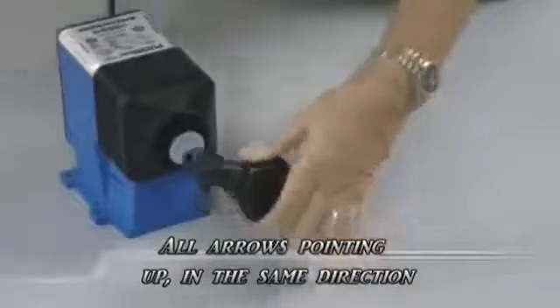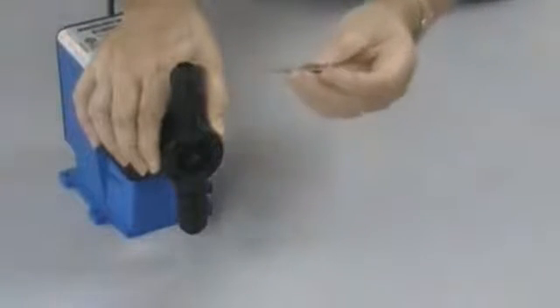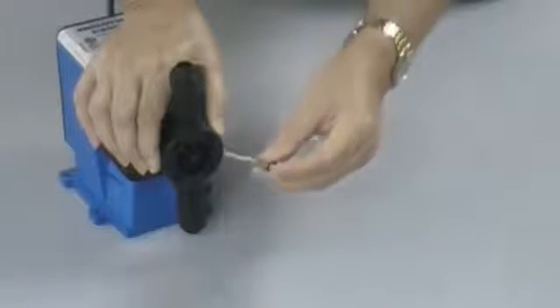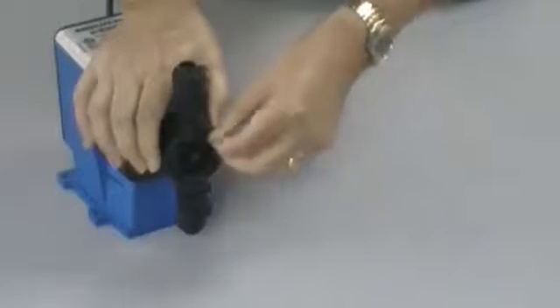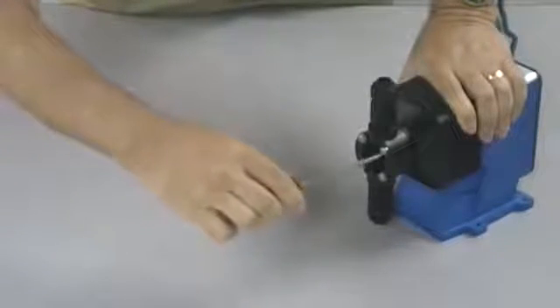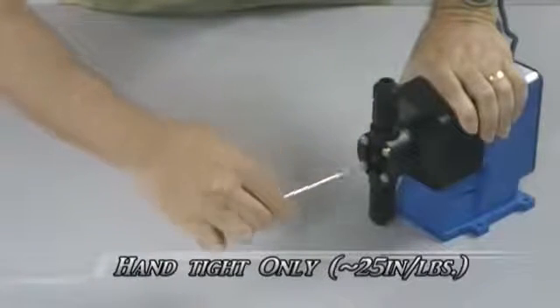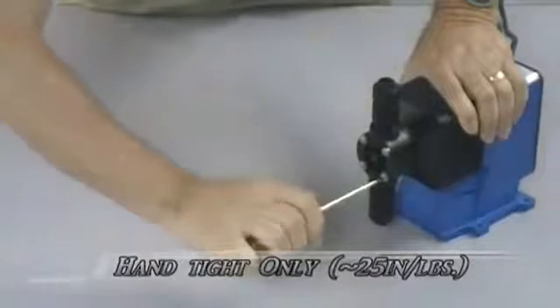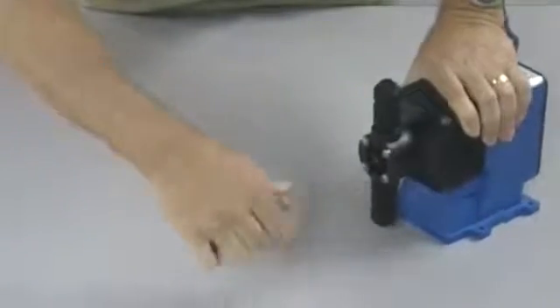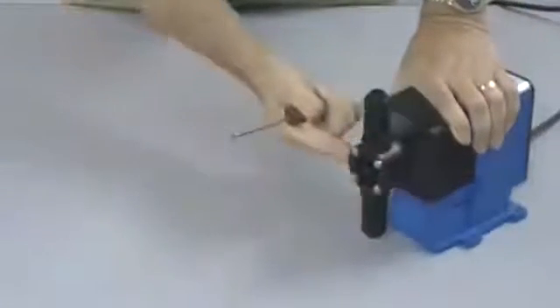Now we will install the pump head to the pump. We place the head on the pump with the arrows in the direction of flow. Take our screw, add a washer to the screw head, and insert it into the pump. Now we will finish tightening the head screws to the pump. This is done in a diagonal manner. We tighten them like this so that the gap between the adapter plate and the pump head is even all the way around.